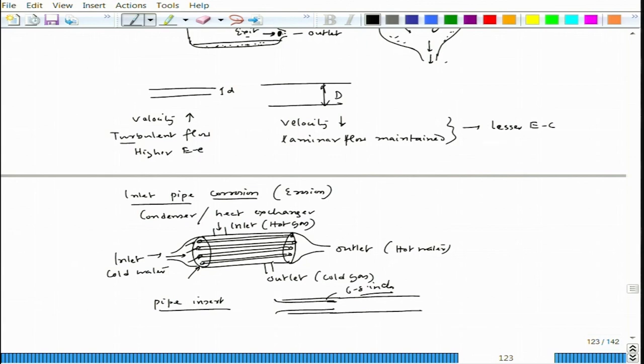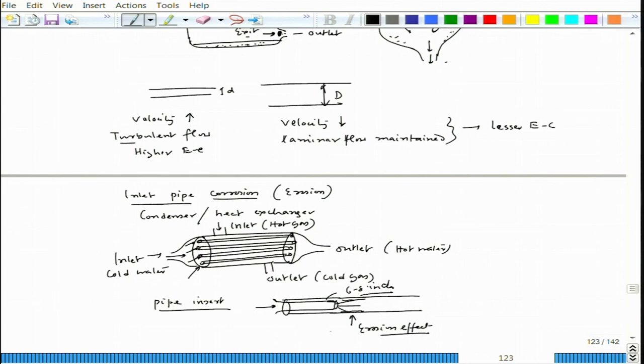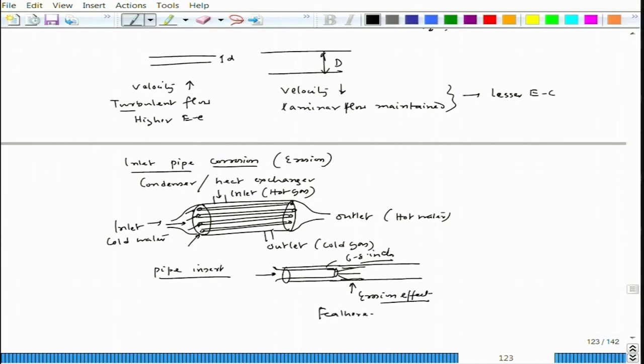This insert allows inlet water to enter through the insert into the main heat exchanger pipe. At the pipe itself, at least, there is no effect of turbulence. Of course, when this water goes out from the exit part of that insert, there can be a little bit of erosion effect. To address that, people use a feathered end insert - the feathered end makes the water flow smooth when it comes through the insert into the main heat exchanger pipe, so the flow is not a very sharp flow but a smooth flow, and the impingement factor would be much less.